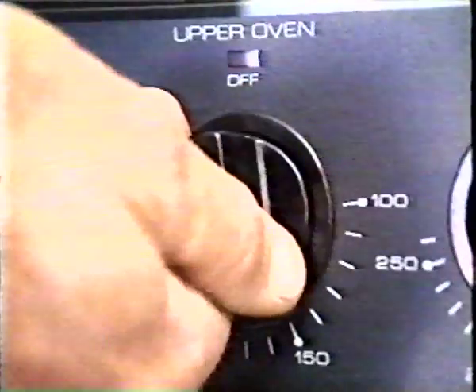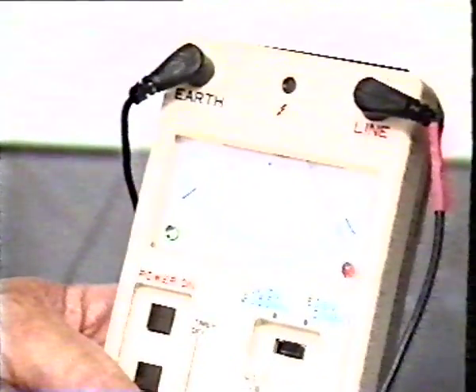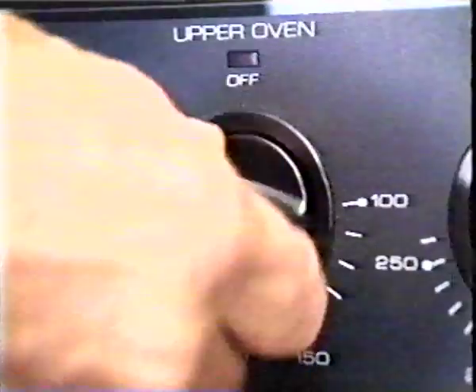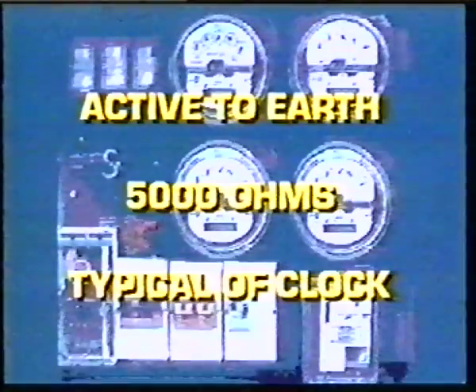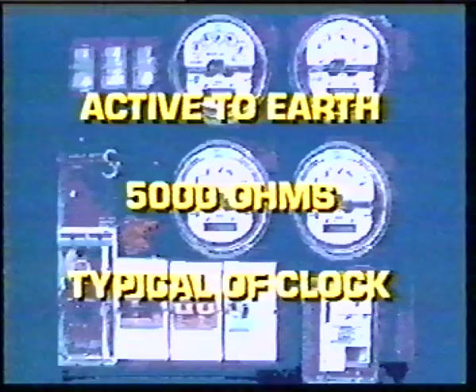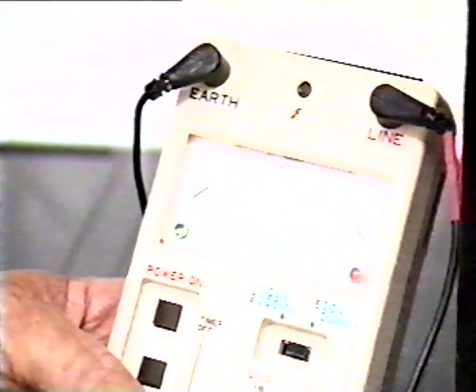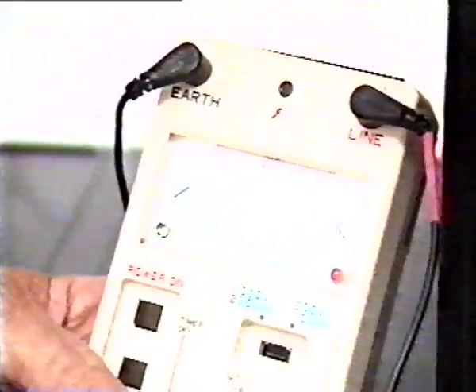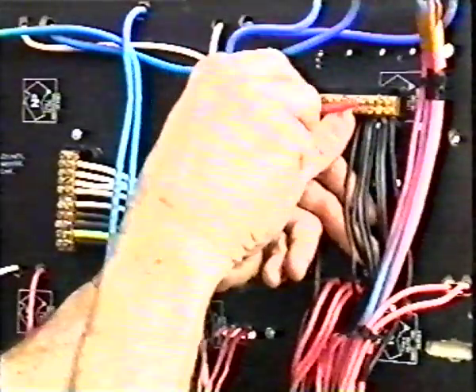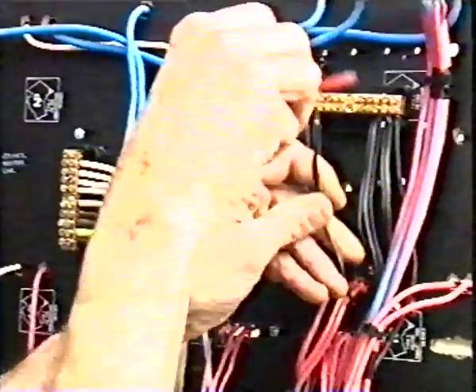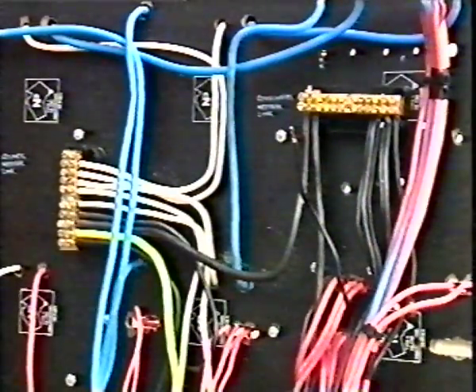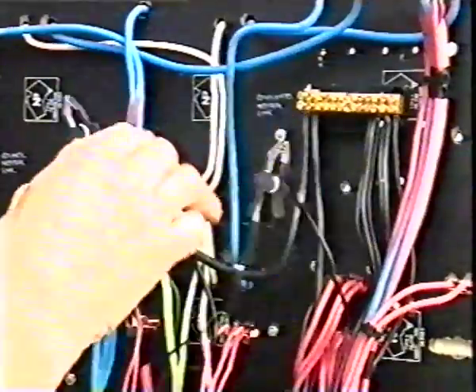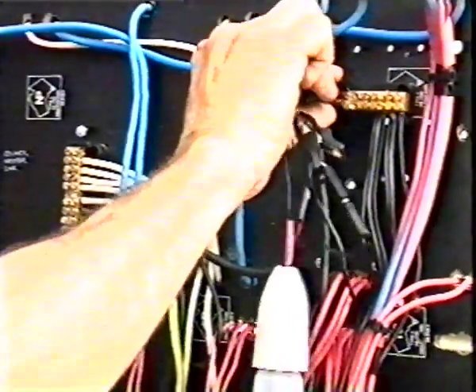Testing a range without supply connected requires an ohm meter, and correct polarity exists if, with switches on, active to earth shows a typical reading of 5 to 15 ohms, while neutral to earth indicates a short circuit. With switches off, the reading should be active to earth 5,000 ohms, typical of a clock, while neutral to earth should indicate a short circuit. Now for socket outlets tested by the ohm meter. First, the neutral conductor of the final sub-circuit being tested is disconnected from the neutral link, and a 60-watt lamp is connected between the conductor and the neutral link.